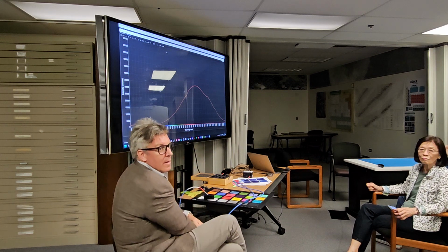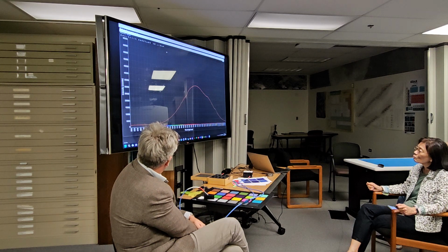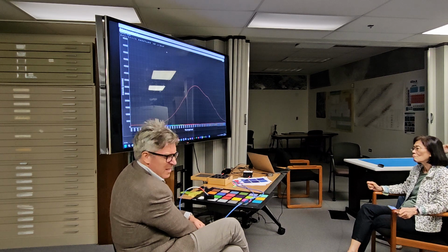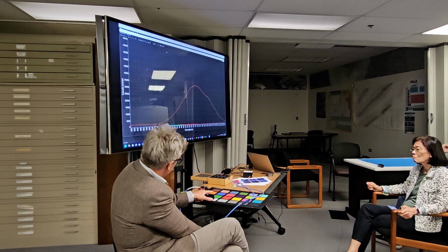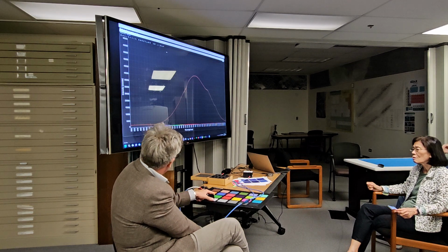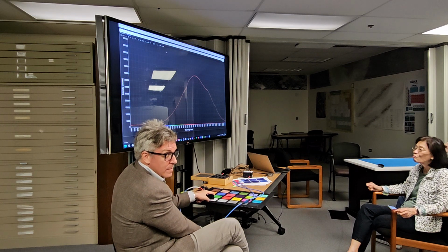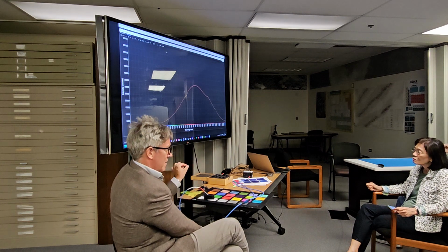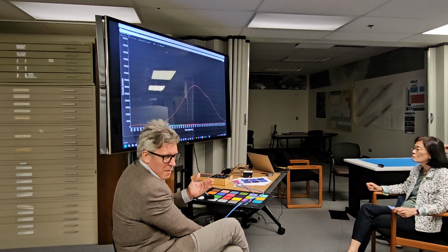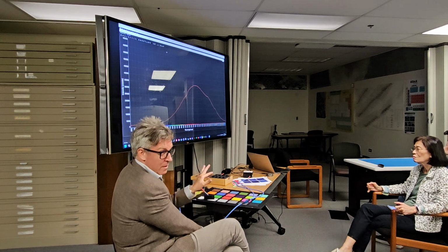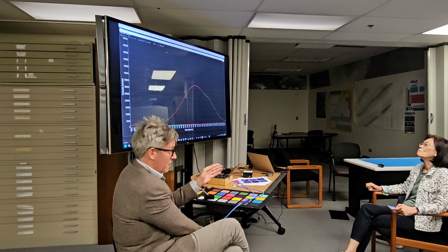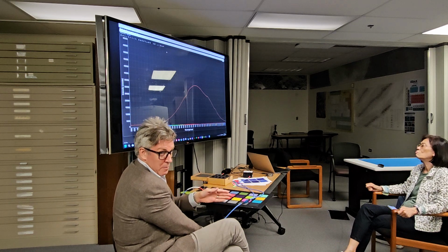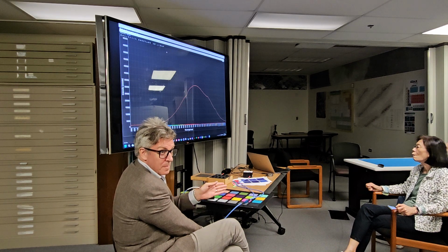So that tiny bump right before 400, is that just one of the detectors maybe being a little hot or something? It could be noise, or is that where one of those mercury features was? Does it go away if I do that? Oh no, yeah, it could be a noisy detector. This gives me the opportunity to average adjacent pixels to beat down that kind of noise, but we're not going to do that because that's reducing our spectral resolution. The dispersion of light across the array is what gives us the spectral resolution of about 1 nanometer.